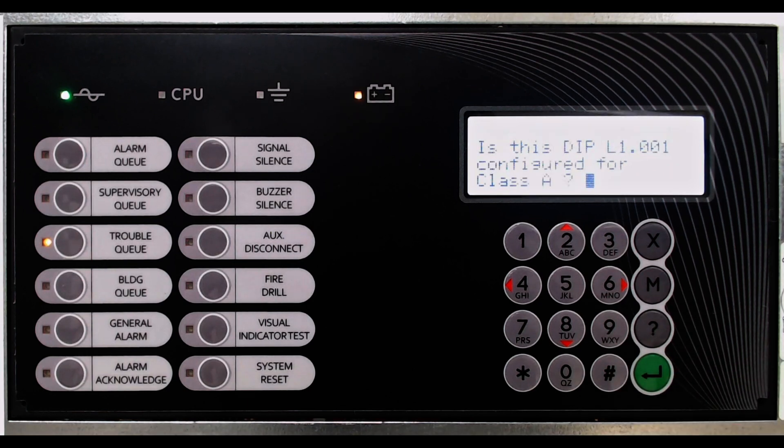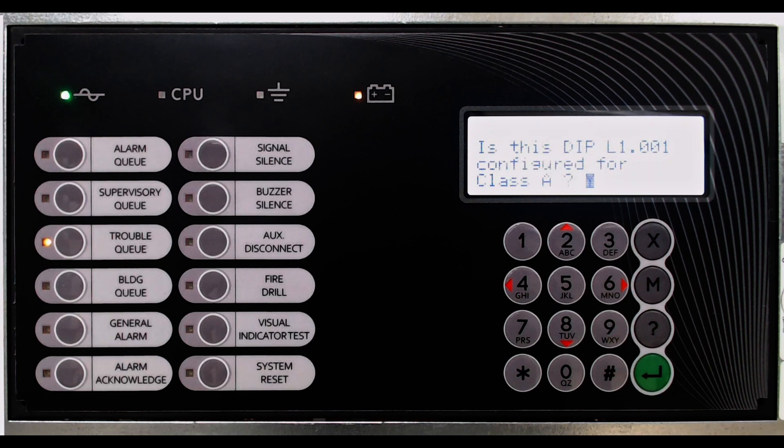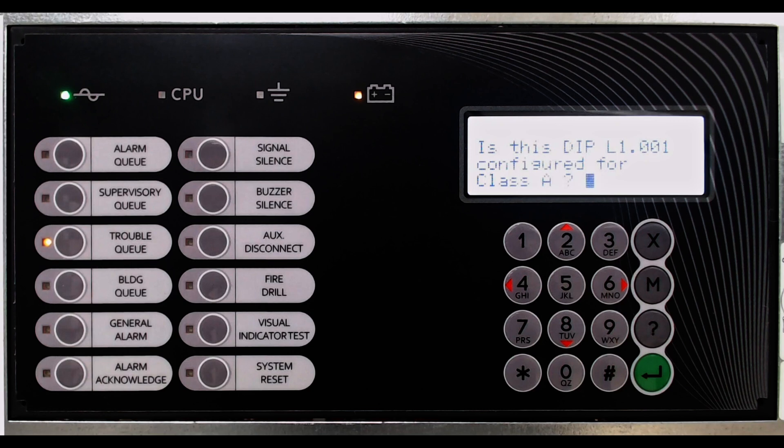Dual input modules that were found during the detection process need to have their initiating circuits set as Class A or Class B wired. The display will prompt for each DIP, dual input module, that was found.